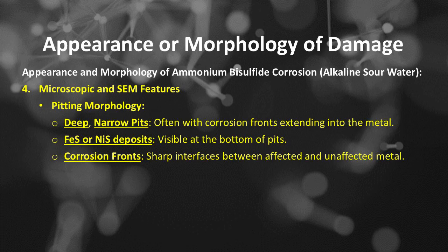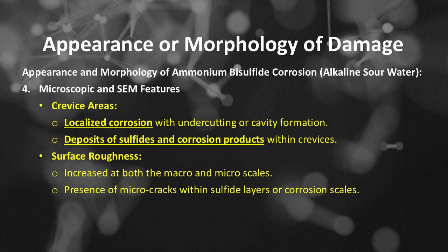Number 4 is microscopic and SEM features. The first is pitting morphology: deep, narrow pits, often with corrosion fronts extending into the metal, and ferrous sulfide or nickel monosulfide deposits visible at the bottom of pits, with corrosion fronts showing sharp interfaces between affected and unaffected metal. The second of the microscopic and SEM features is crevice areas, which include localized corrosion with undercutting or cavity formation, and deposits of sulfides and corrosion products within crevices.